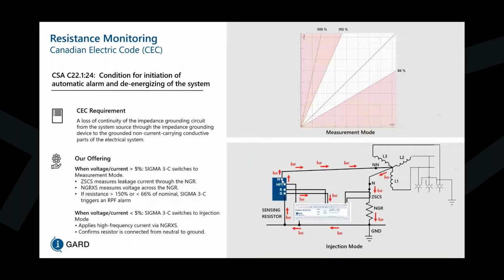In the case where our high frequency signal is moving around the circuit and down through the NGR, and suddenly an open circuit occurs, our relay starts a counter to see if that signal is going to come back, and if it doesn't come back, then we indicate an open circuit. We also have a measurement mode where, when a certain amount of voltage and current is picked up by our sensing resistor and CT, we use that current and voltage to back calculate a resistance and compare that measured resistance to the actual resistance of the NGR.